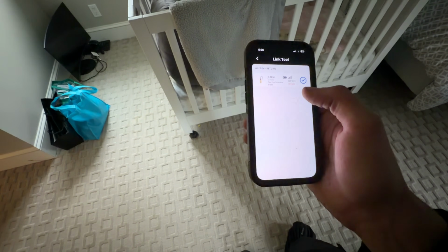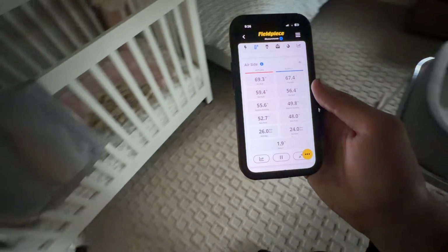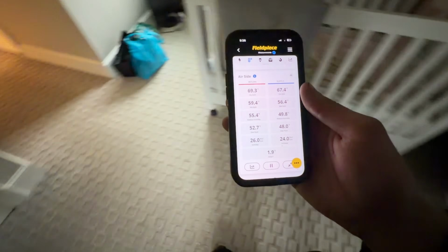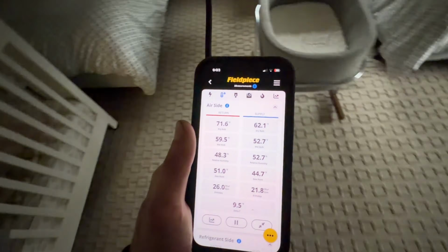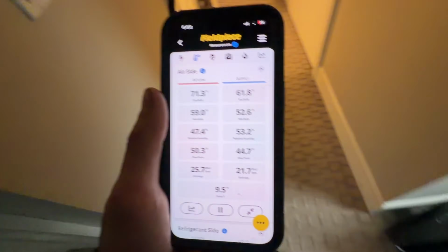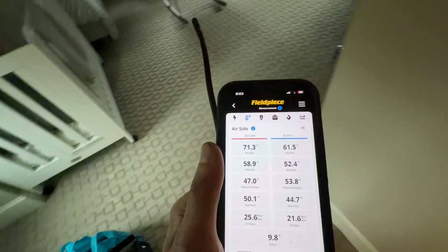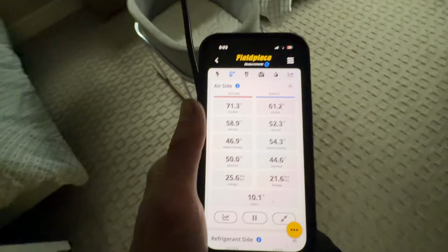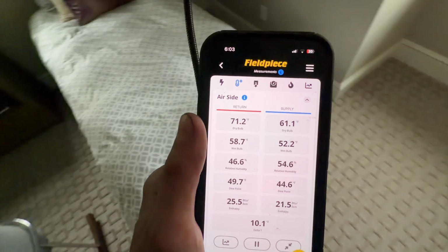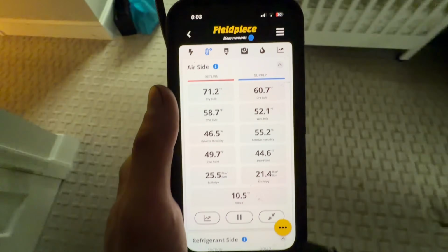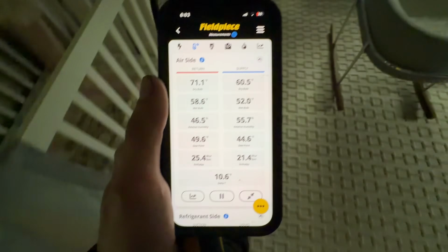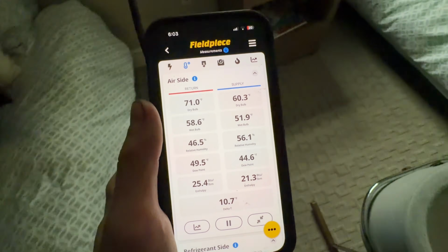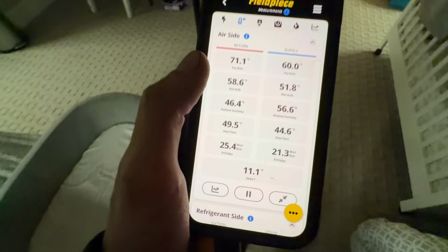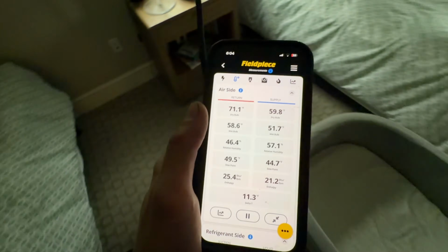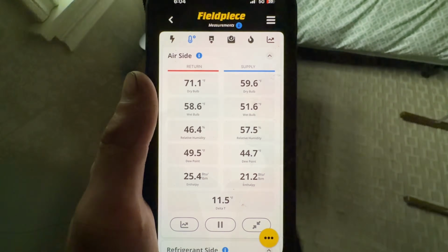What is going on here? Our return is reading 69, but that's not possible. Okay, I just had another mini little problem to solve. The heat wasn't shutting off, and I don't know why. There's no call for heat, and the zone pumps downstairs don't show a call for heat, so for some reason it's getting some sort of cross flow. It's already 6 o'clock. I'm just gonna shut the valve off for that heating zone and tell them that that's gonna need further diagnosis. But now you could see our return is 73. We're getting a better delta T as that hot water coil in the ductwork cools off from the system running and cooling. Okay, so that's an issue for another day.